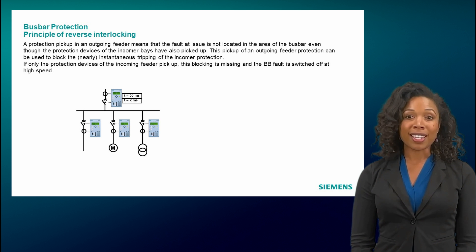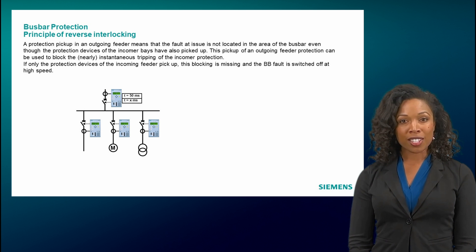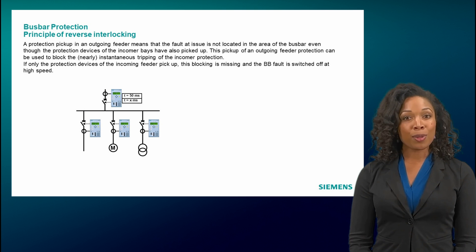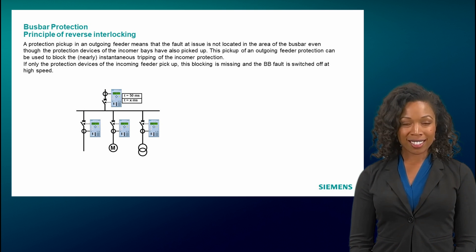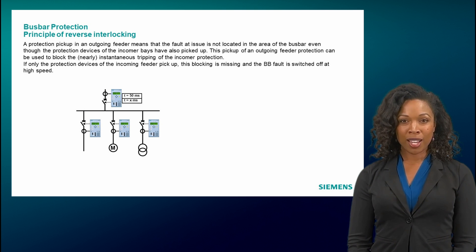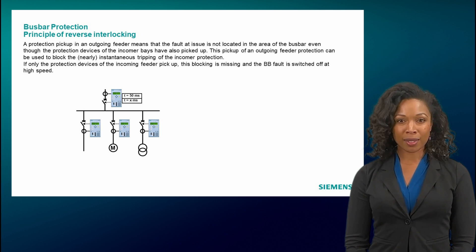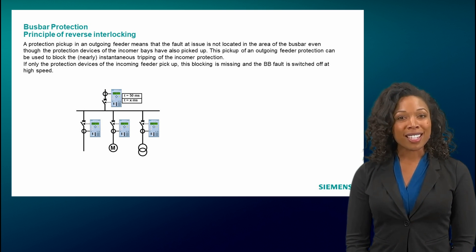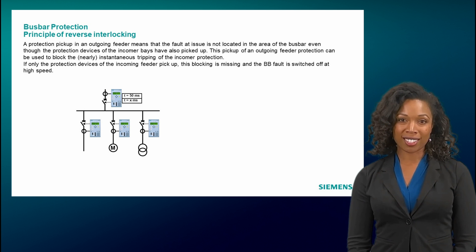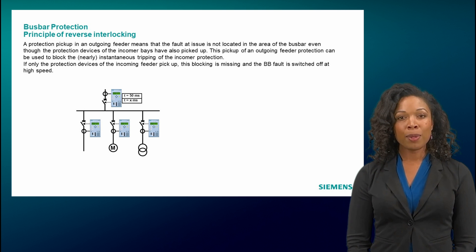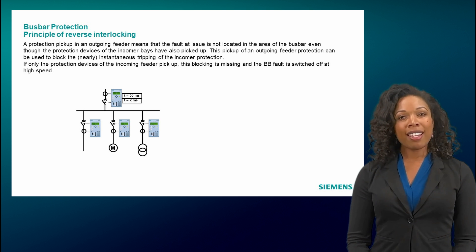Busbars are the places of highest energy concentration in switchgear. Busbar faults that last too long can easily lead to extensive damage to the primary plant. The resulting supply interruptions can have significant negative effects such as production losses, especially in industrial networks. Therefore, regardless of the voltage level, important busbars must be protected in fast time.